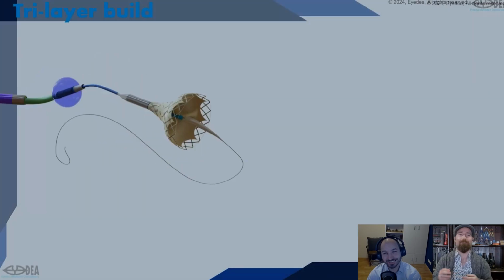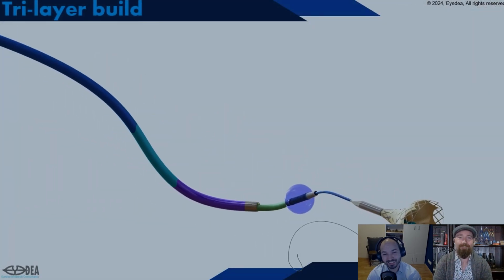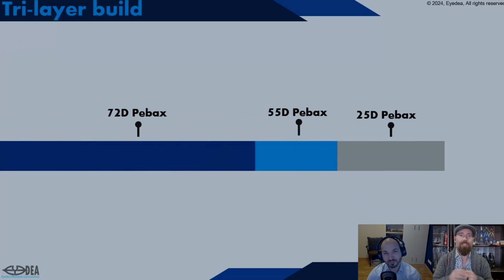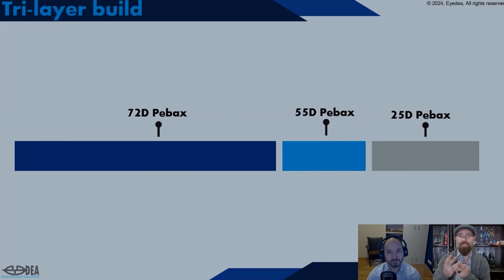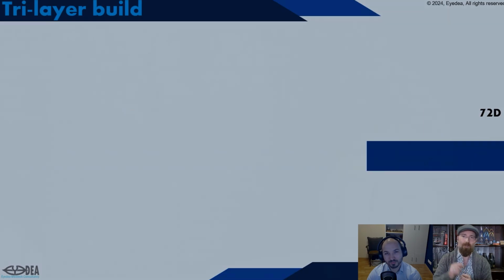And then say we want a device like this that might be going deep into the body, so you might have different sections of plastic that you want to put on the outside. So as I said, stiff where you're holding and controlling, soft where it's bending around the body. So you might pick 3 different jackets, ideally of the same material so that you know they stick together, they melt at the same temperature, that they can intertwine and hold on together. Because you have like the thickness of a paper sometimes holding these 3 different materials together, or 2.